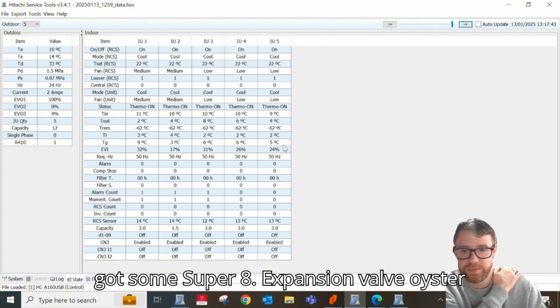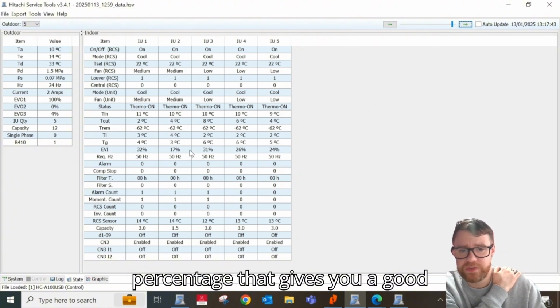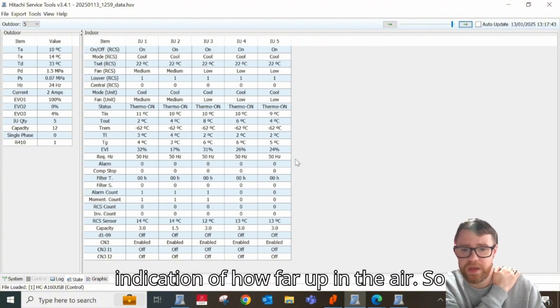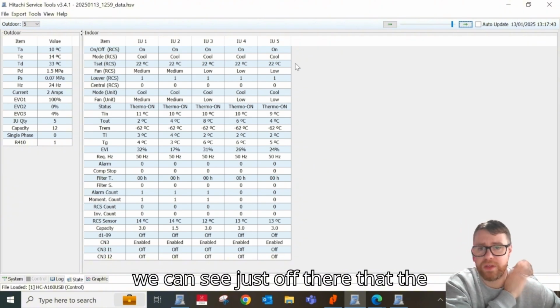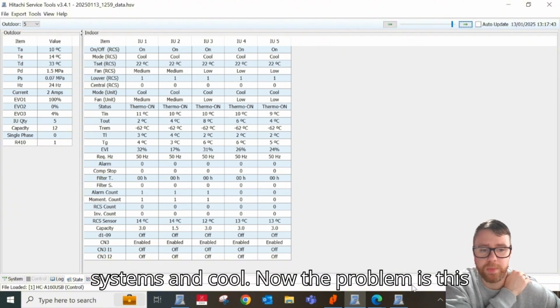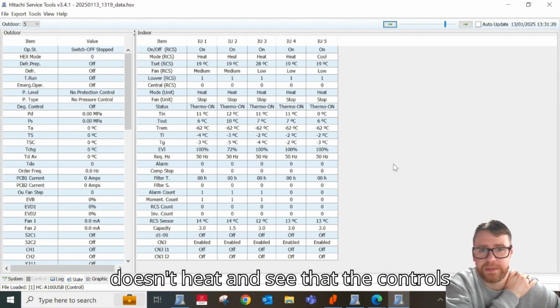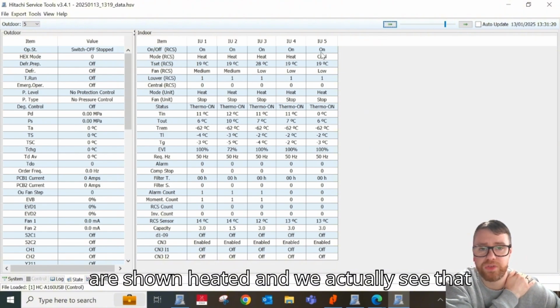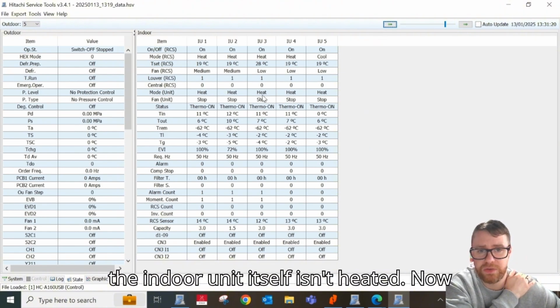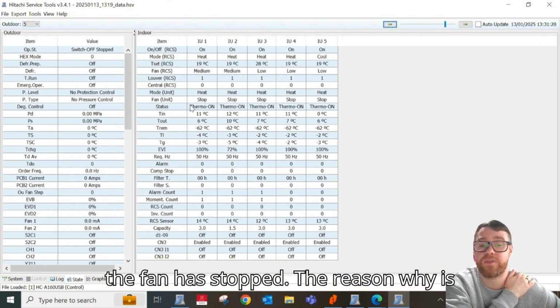So we can see that we've got some superheat. The expansion valve is always shown as a percentage, so it gives you a good indication of how far open it is. Just off that, we can see that the system doesn't cool. Now the problem is when the system goes into heating. We can see that the controls are showing heating, but the indoor unit itself isn't heating. Now the fan has stopped.